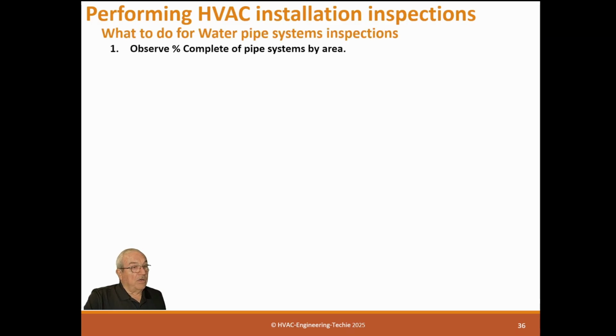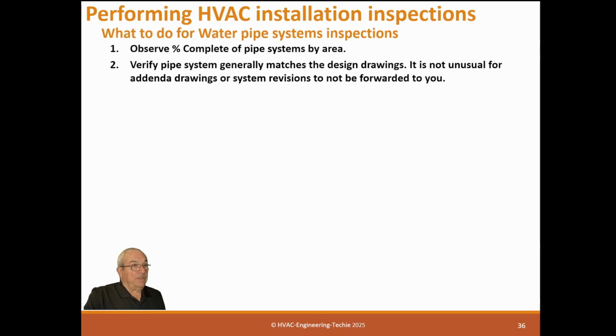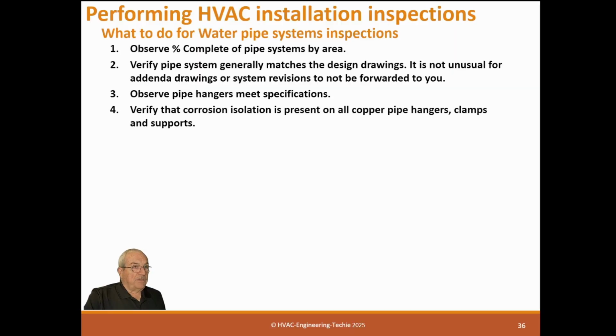So what to do for water pipe inspection? Observe the percent complete by area. Verify pipe systems generally match the design drawings. Remember, you may not have the main addenda. Observe pipe hangers meet specifications. Verify that corrosion isolation is present on all copper pipe hangers, clamps, and supports. Remember that copper and steel don't get along. You can't let them touch.